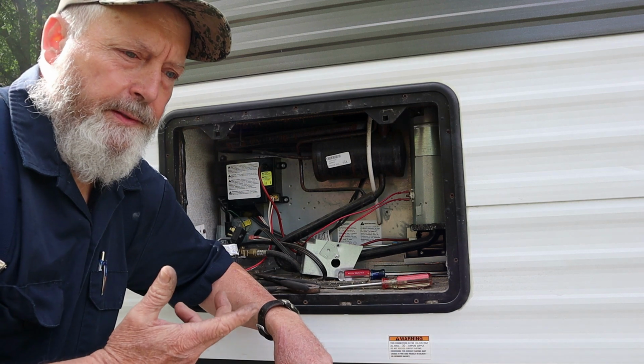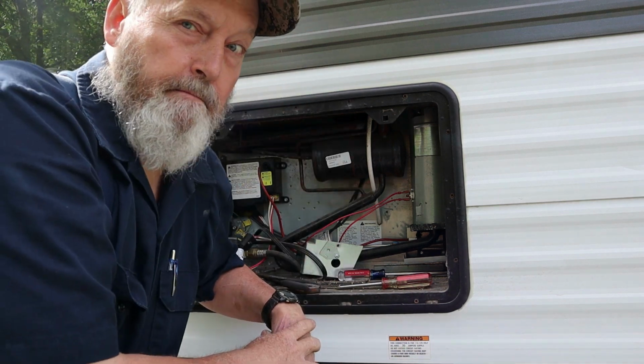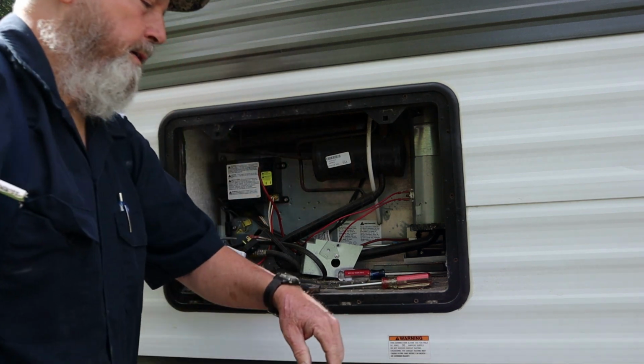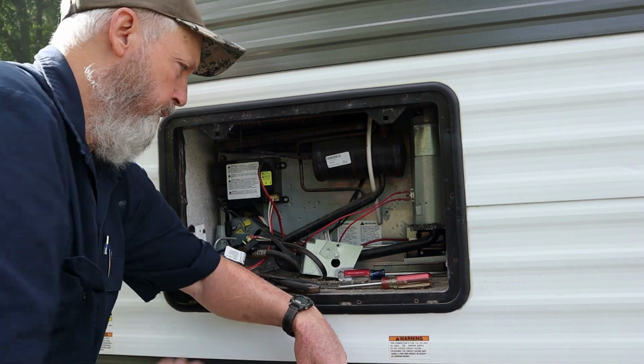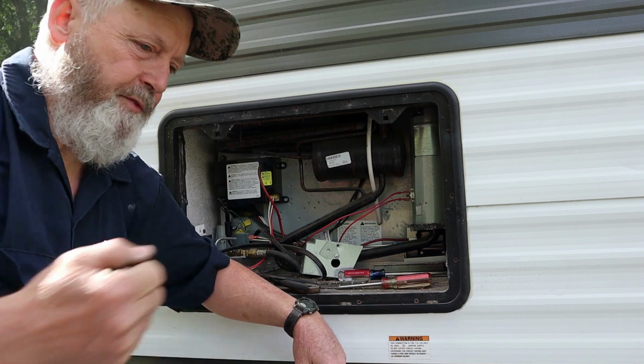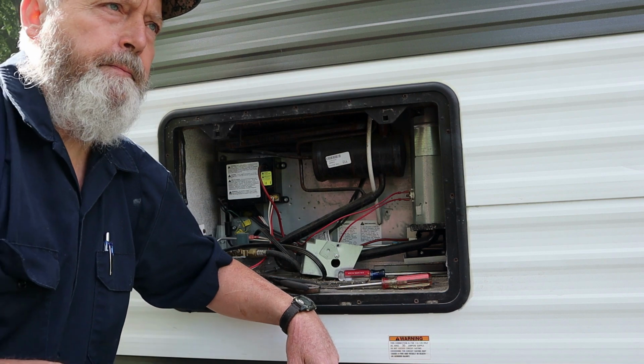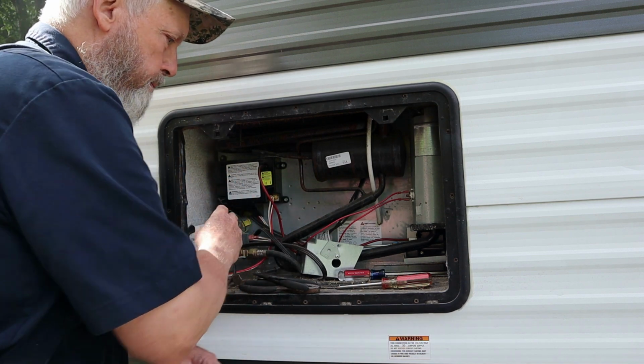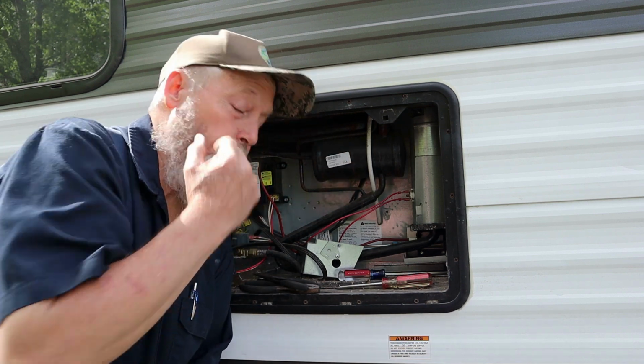Shouldn't take long. So let's listen. Okay. Sounded okay. I didn't really hear whether it was the first strike or the fourth strike. Now that the refrigerator is calling for cooling, let's do this one more time. We'll plug her in. Go to electric. Give it just a minute. Not really a minute. That's enough. And we'll listen closely this time. All right, here we go. That was first strike. Definitely first strike. So we've made an improvement.